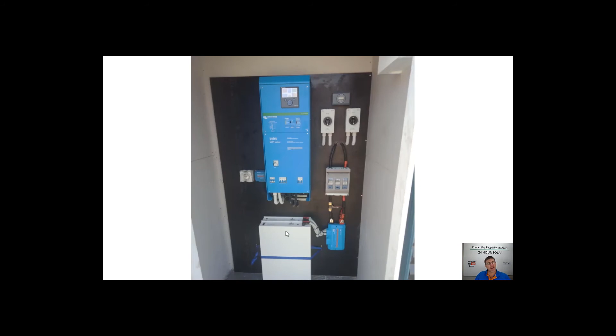So on these bigger systems, we use a Redback battery enclosure. Basically, with these Redback battery enclosures, they can handle up to 4 batteries. So the minimum we would recommend in this size system is 3 batteries. Now, you can get away with 2, and it all comes down to your energy loads and things like that. So the minimum is 2 that you can get away with in these size systems. And so this system here is a 5 kVA. It's got a minimum of 2 batteries in there. We would recommend putting 3 in, but like I said, you can get away with 2.